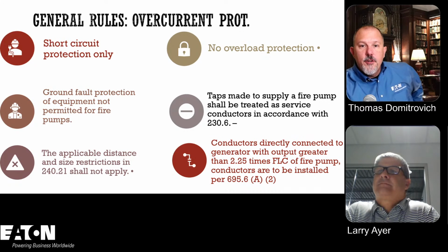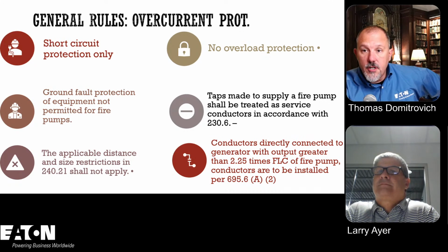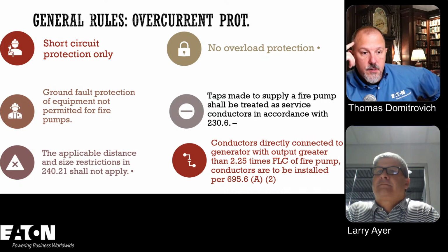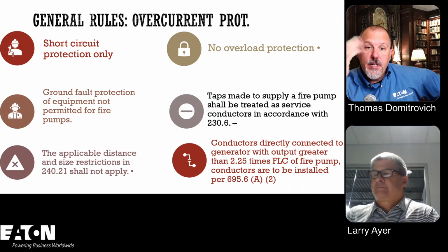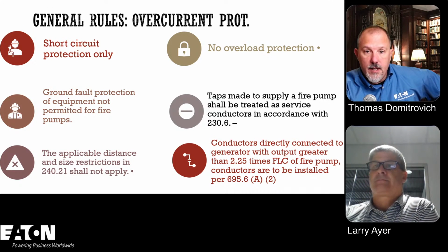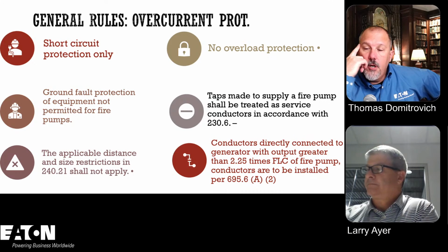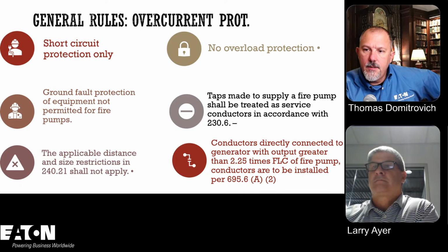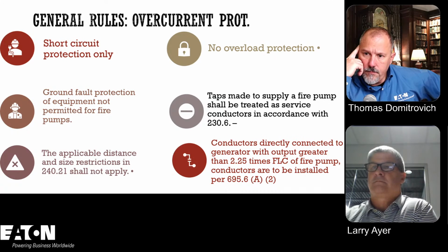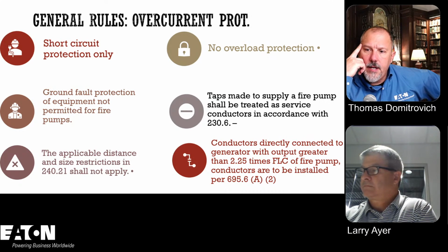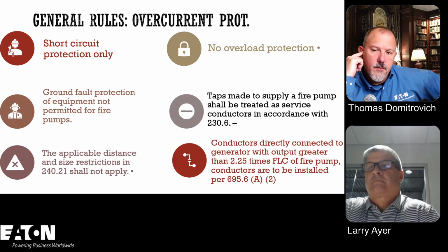And these are all your general tips. So it's short circuit protection only. We already talked about that, answering the question about the overload. We talked about ground fault protection of equipment is not permitted. No overload. There's no overload protection. Did we talk about the taps? Yeah, the taps, again, 230.6. That's in your services. Mm-hmm. And then conductors directly connected to the generator with output. Again, 2.25, 2.25 times the full load current of the fire pump.